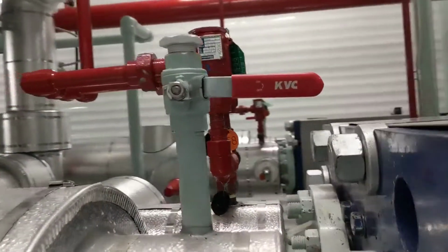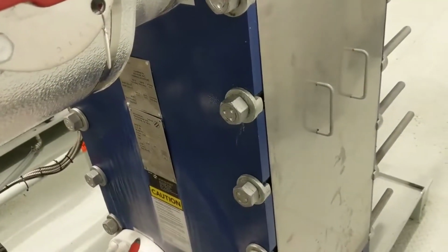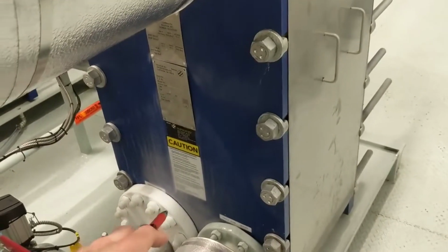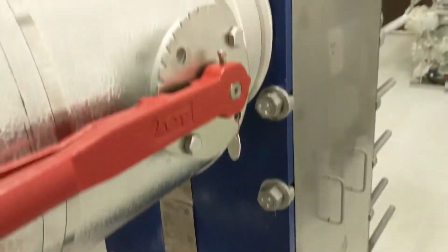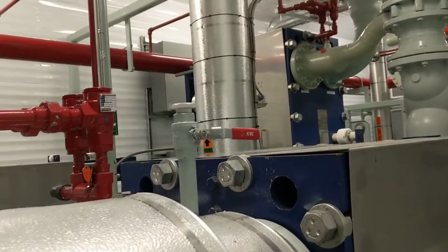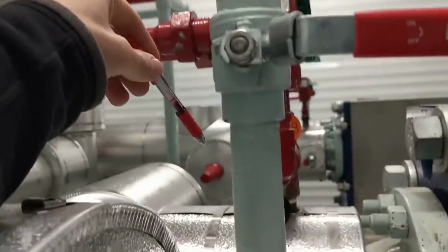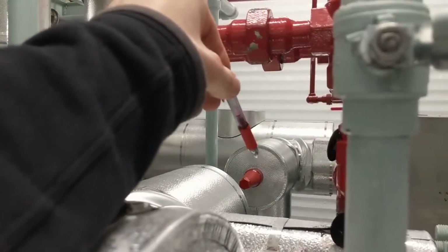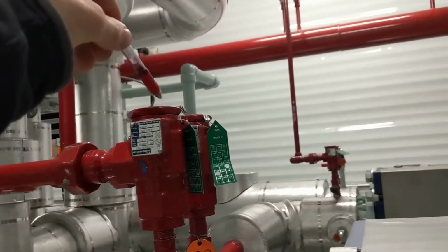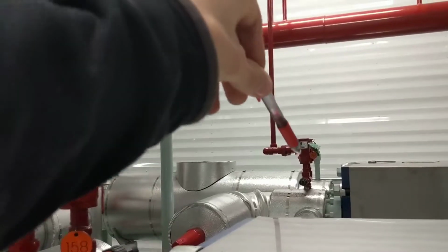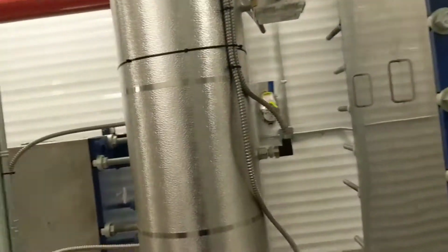So as the ammonia goes through this heat exchanger, it's essentially boiled off using the heat from the brine. So the ammonia removes the heat from the brine, it picks up its heat as it's boiled off, and it gets pulled out through here and out through there on the other side. So you can see the two with the relief lines on it. So this here with the relief lines, and over there with the relief lines.